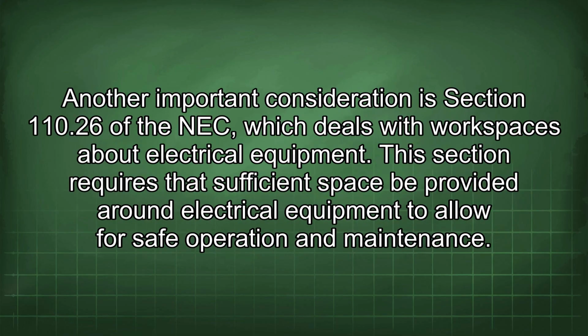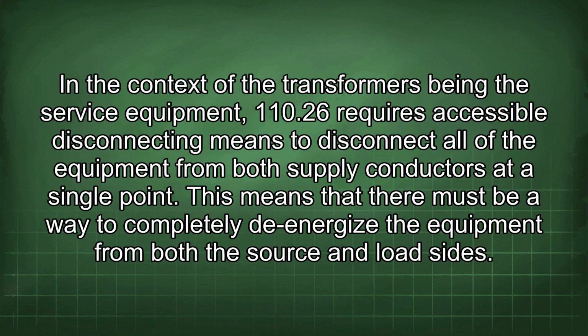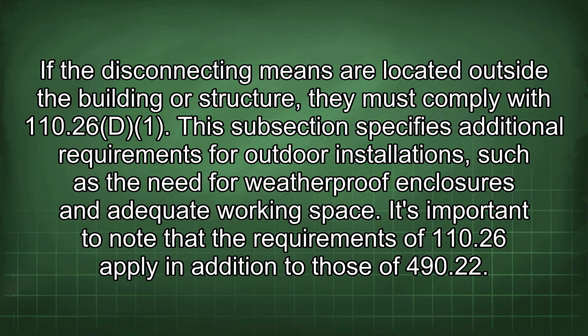Another important consideration is Section 110.26 of the NEC, which deals with workspaces about electrical equipment. This section requires that sufficient space be provided around electrical equipment to allow for safe operation and maintenance. In the context of the transformers being the service equipment, 110.26 requires accessible disconnecting means to disconnect all of the equipment from both supply conductors at a single point. This means that there must be a way to completely de-energize the equipment from both the source and load sides. If the disconnecting means are located outside the building or structure, they must comply with 110.26(D). This subsection specifies additional requirements for outdoor installations, such as the need for weatherproof enclosures and adequate working space.